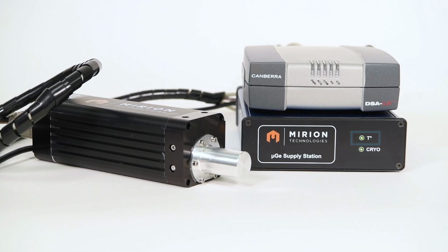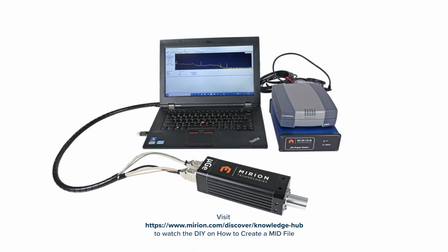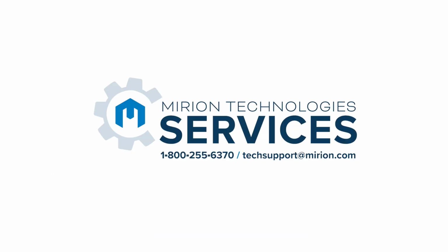Before applying the high voltage, make sure that the low voltage power supply cable is well connected and that the temperature LED is on. The cooling time for the detector is approximately 30 minutes or less. Now you are ready to connect the detector to your computer installed with Genie to start your measurement.